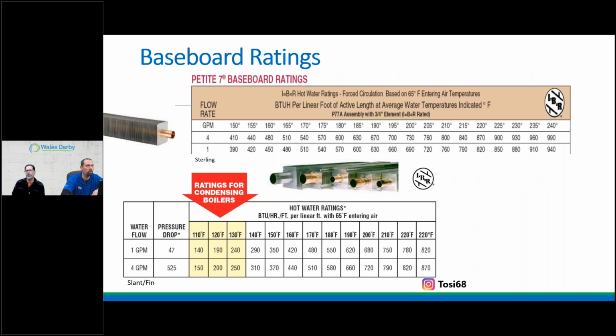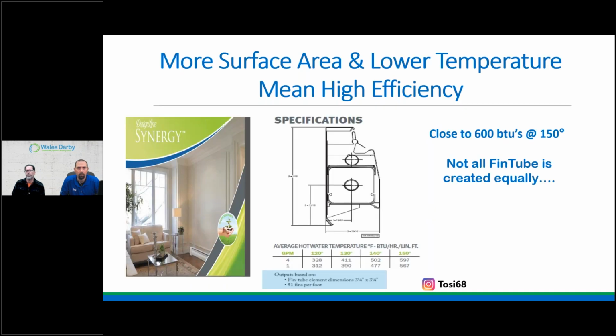So if I look at this chart at 130, the lower one, it says 1 GPM, 240 BTUs. Go to this one, 120, 1 GPM, 312. So if it is baseboard and it is a lack of wall space, we do have low temperature, high output baseboard. All right, these things are around us, they're achievable. Investigate, speak to your wholesaler.